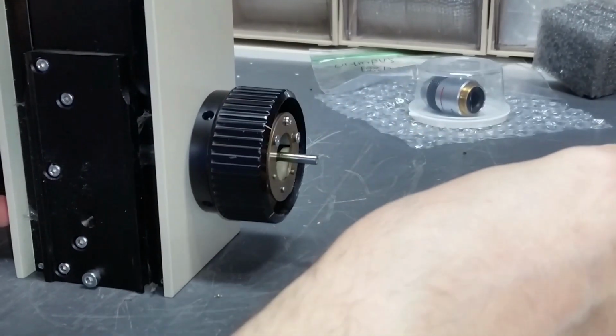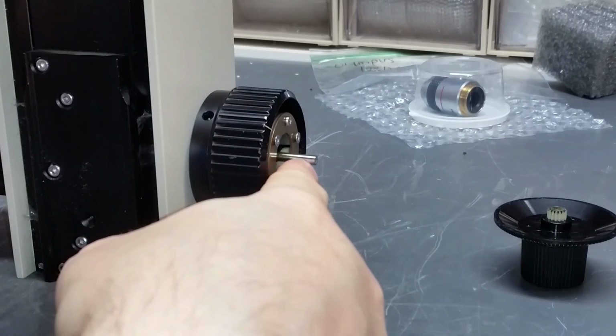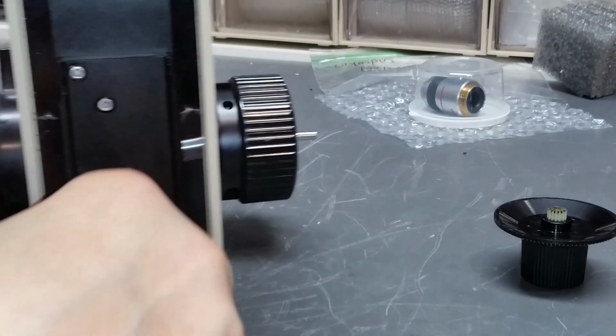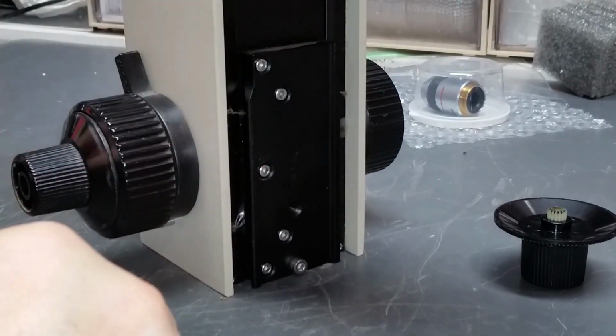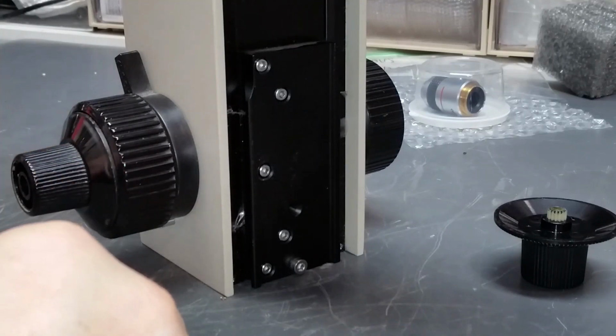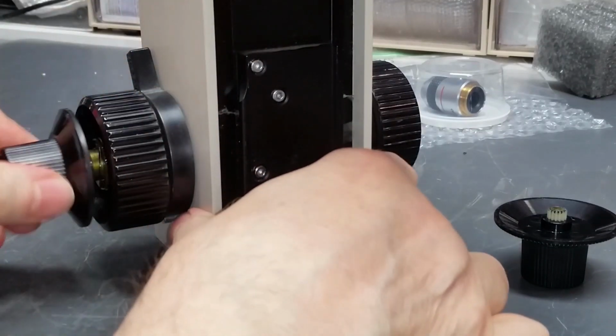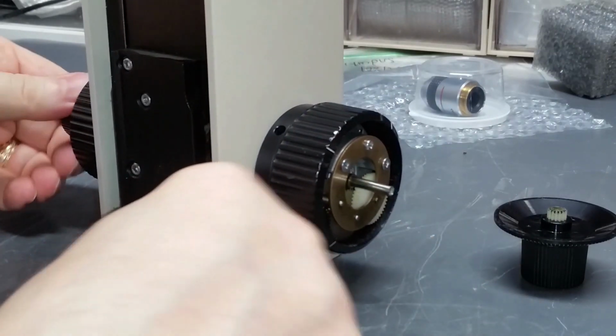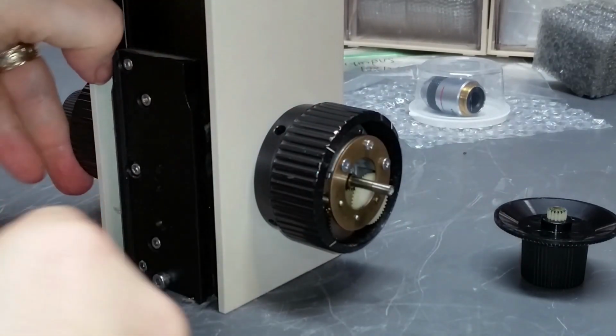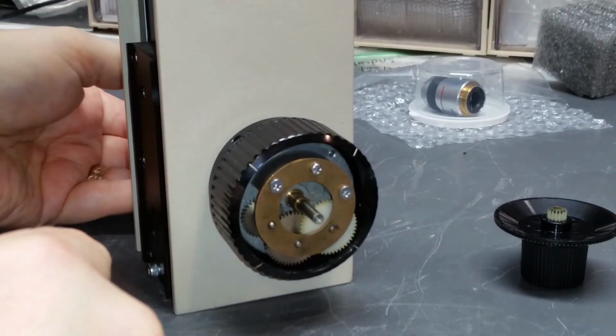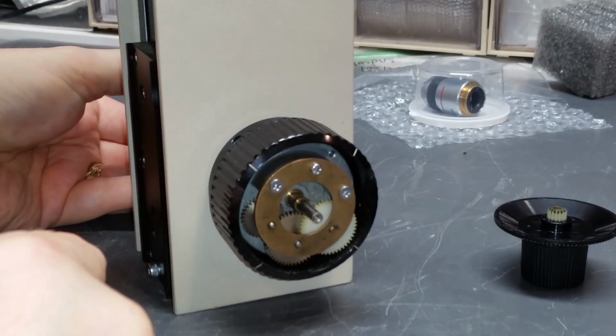These come off, and we're left with the fine focus shaft sticking out of here. Ordinarily, if this were a scope that was in decent shape, I could grab this knob and pull the whole shaft out, but I can't really do that in this case. It gets really tight down. The reason for that is because that bent shaft doesn't really want to go through that hollow brass tube that it's in. It wants to catch because it's bent.